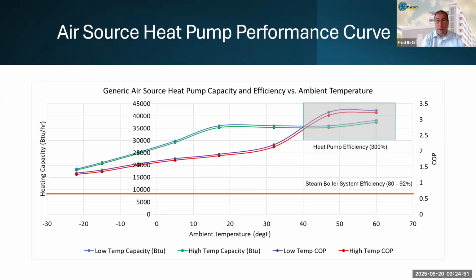Our 410A evaporates at -55 degrees. So you can definitely heat. The catch is the capacity and the efficiency decline as you go to lower and lower temperatures. The AHRI test standard for heat pumps is for 17 degrees Fahrenheit, which, if you happen to be in a location where the heating design conditions, the 99.6, are 17 degrees, well, great, good for you. For everyone else, for whichever product or products you're looking at, you need this full curve down to whatever your design condition is.